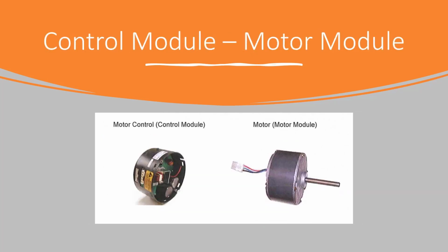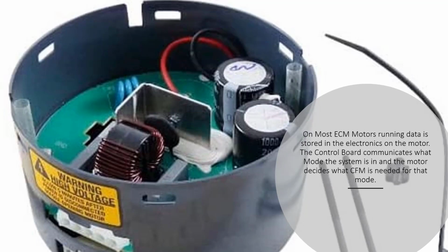As we have said, the ECM motor consists of the main motor module and then the control module that attaches to it. If the motor checks out fine, the module can be replaced by itself, so you don't have to replace the entire motor. On most ECM motors, running data is stored in the electronics on the motor. The control board communicates what mode the system is in, and the motor decides what CFM is needed for that mode.